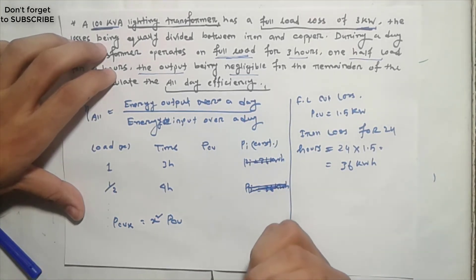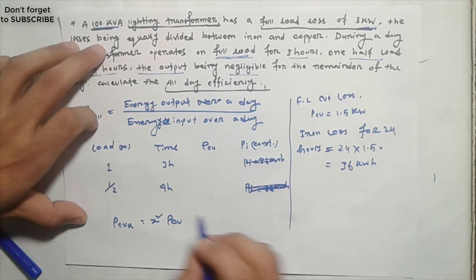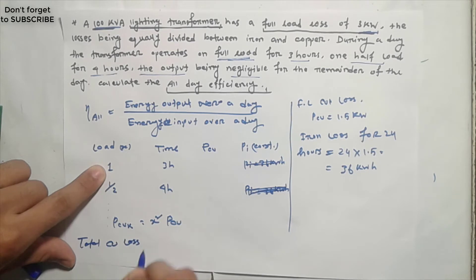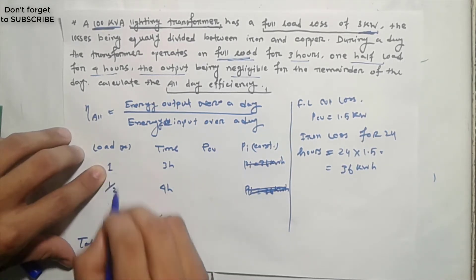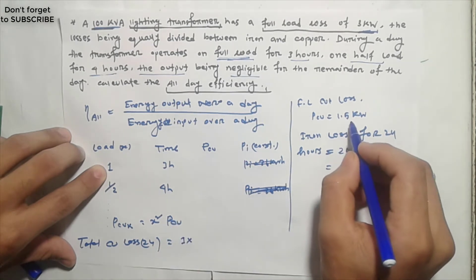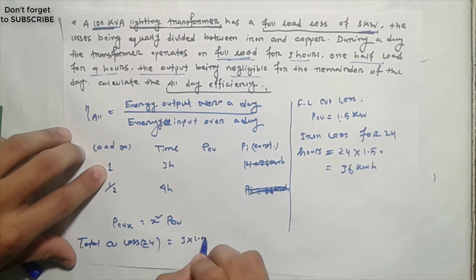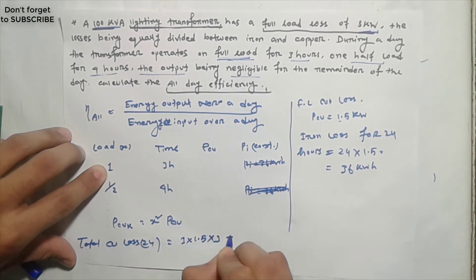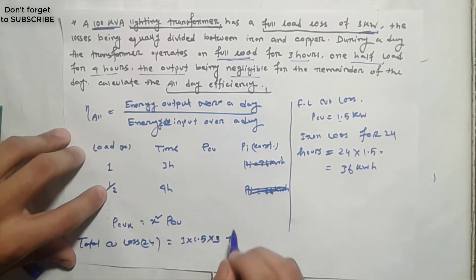Total copper loss calculation: using load type and x-squared, total copper loss is 1.5 times 1 squared for full load, plus 1.5 times one-half squared for half load, giving values of 1.5 and 0.375 respectively.